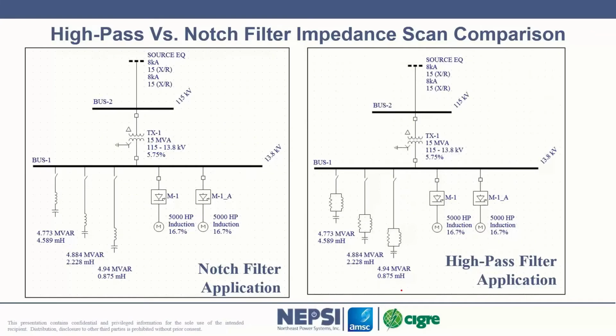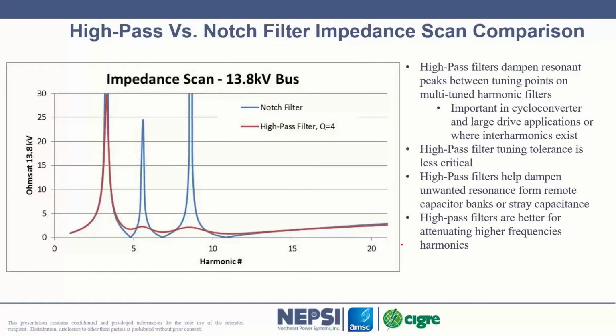So you might say, well, what's the difference between these two types of filters? On the left, I have a system that consists of notch filters. On the right, I have a system that consists of high pass filters. And again, these could be C high pass filters. It would be exactly the same result. And what you see is an impedance characteristic that looks like this. And you can see what we've done is we've eliminated these resonant points with high pass filters. We reduce or dampen that resonance down to these values here in red.